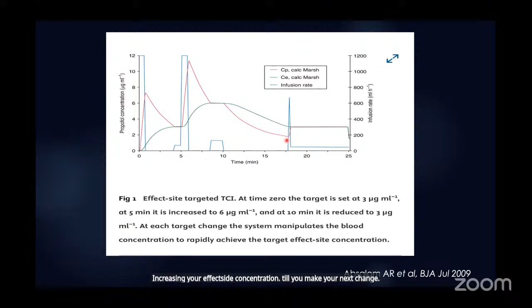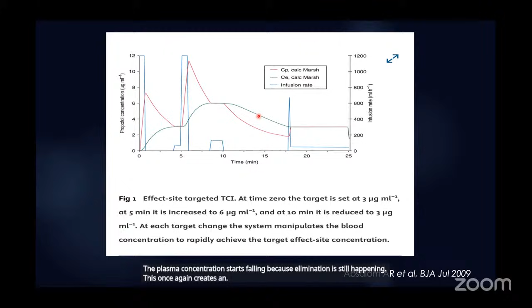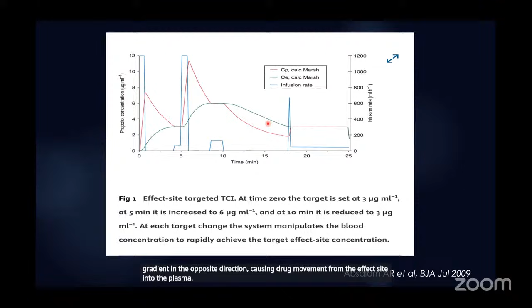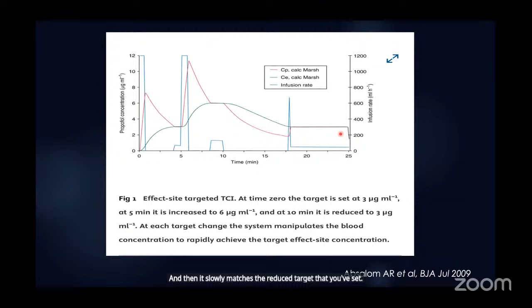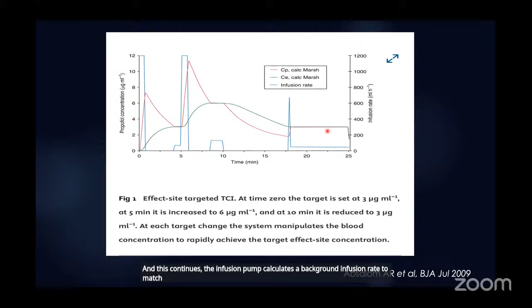Again, a rapid increase in the plasma concentration, driving the drug into the brain, increasing your effect site concentration till you make your next change. Now, at 10 minutes, you decide to once again make the concentration 3. The surgery is coming to an end. You want to taper down. So the pump stops infusing. There is no background infusion rate. The plasma concentration starts falling because elimination is still happening. This once again creates a gradient in the opposite direction, causing drug movement from the effect site into the plasma, and then it slowly matches the reduced target that you've set. And this continues. The infusion pump calculates a background infusion rate to match the target that you have set till you make the next change.